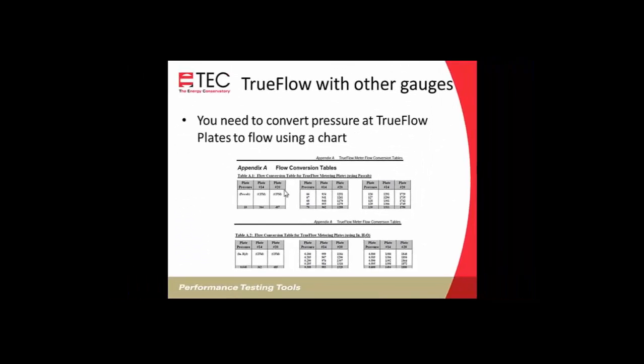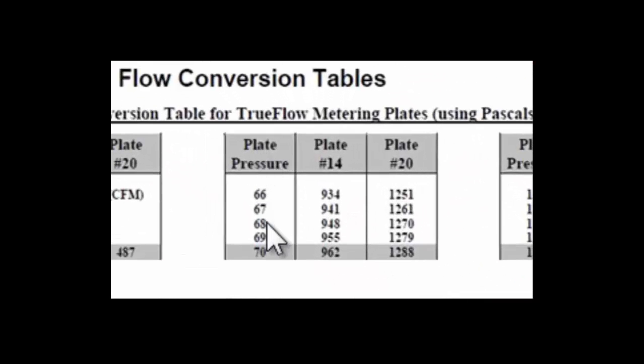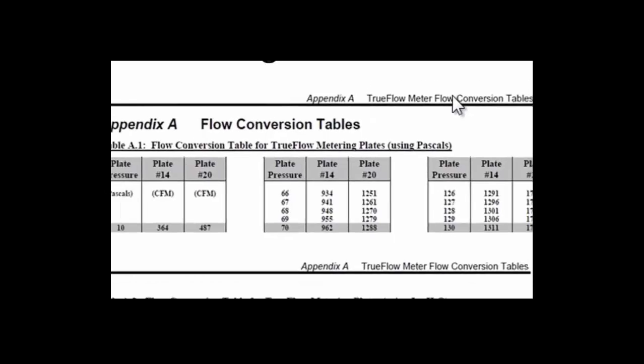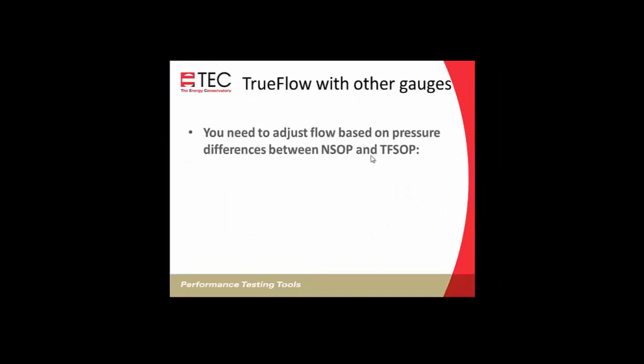So for example, with the Pascal chart, the plate pressure, the pressure we're measuring on the gauge, will go across to whichever column. If we're using the 14 or we're using the 20, we'll move over to that column to see what the CFM is. So if we've got 68, we'll have 948 with the number 14 plate and 1270 with the number 20 plate. So that's how we convert pressure to flow using the charts.